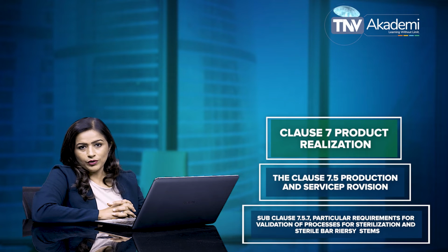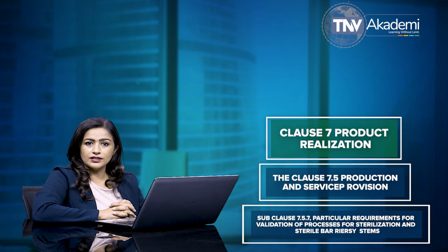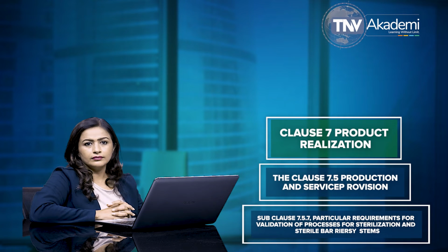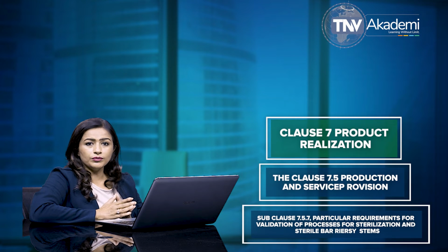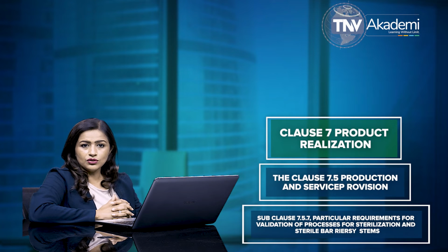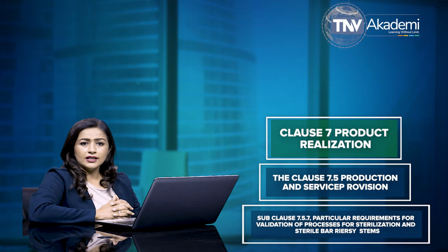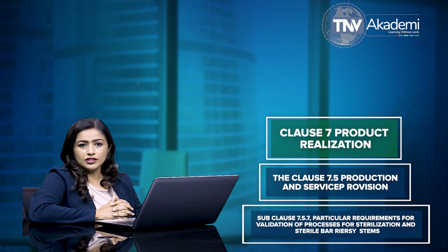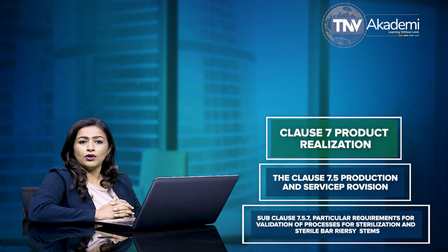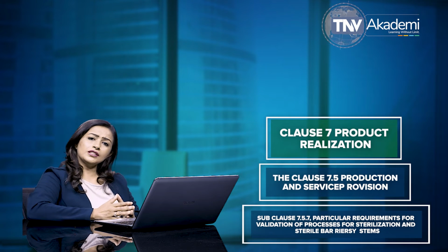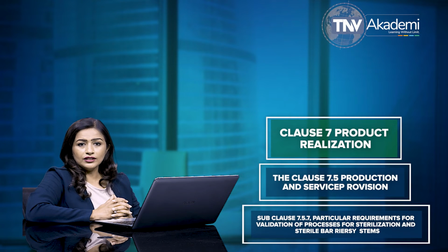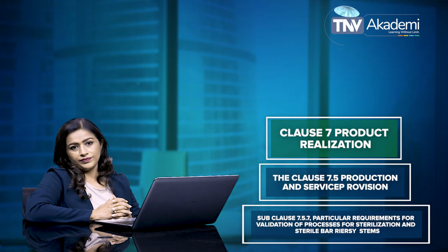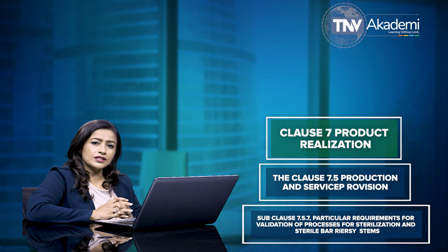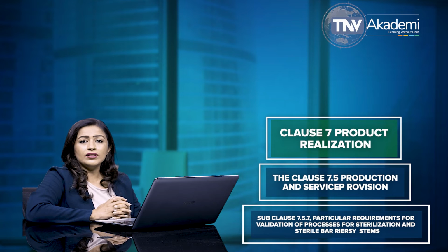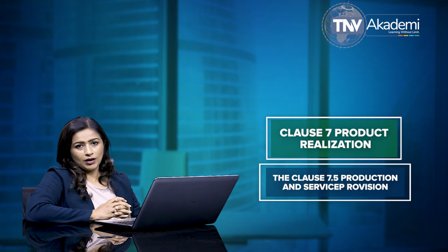Let's talk about subclause 7.5.7, that is, particular requirements for validation of processes for sterilization and sterile barrier systems. According to this subclause, the organization is required to document procedures for the validation of processes for sterilization and sterile barrier systems. This clause says that processes for sterilization and sterile barrier systems must be validated prior to implementation and following product or process changes as appropriate. As per this clause 7.5.7, records of the results and conclusion of validation and necessary actions from the validation must be maintained to meet the requirements of the standard. This clause also guides to refer to ISO 11607-1 and ISO 11607-2 for further information about it.